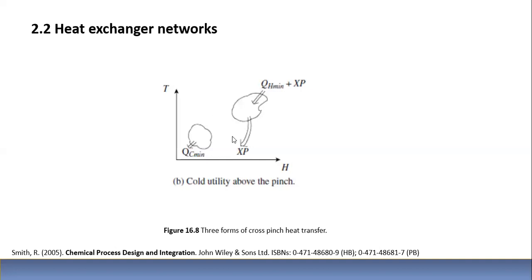So there is some sort of interruption between the heat sink part of the process above the pinch and the heat source part of the process below the pinch. There's some sort of interruption. So energy is not cascading down naturally. Probably there are no heat exchanges between the two of them, between the heat sink and the heat source. There are no heat exchanges. So we're just wasting energy. This is a clear way to waste energy.